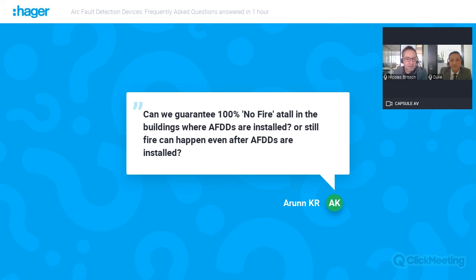But still, the AFDD is here to improve the electrical fire protection. But it's not possible to guarantee 100%. This is also true for every kind of protection. You can never guarantee 100% protection, because there will still be some situations where it will be very complicated, for example, to detect the fault. But these are really small situations, and of course the standard is here to be sure that every product, every AFDD, has the required level of protection in order to detect arc faults.